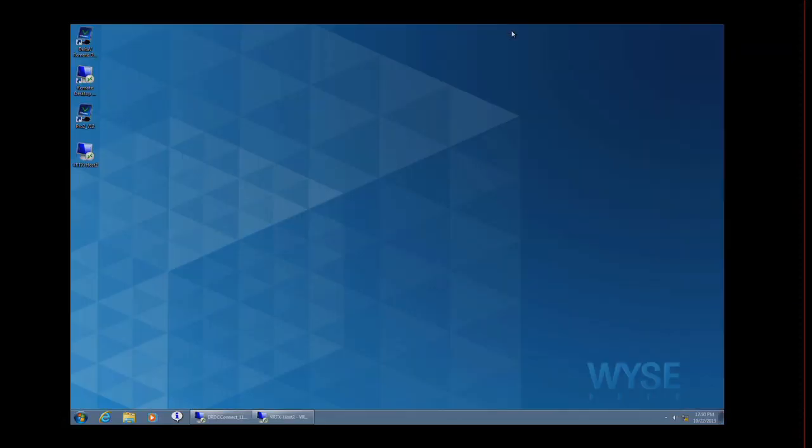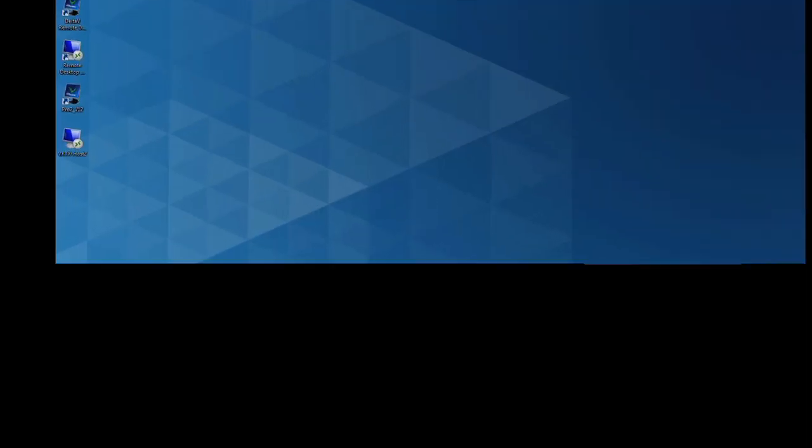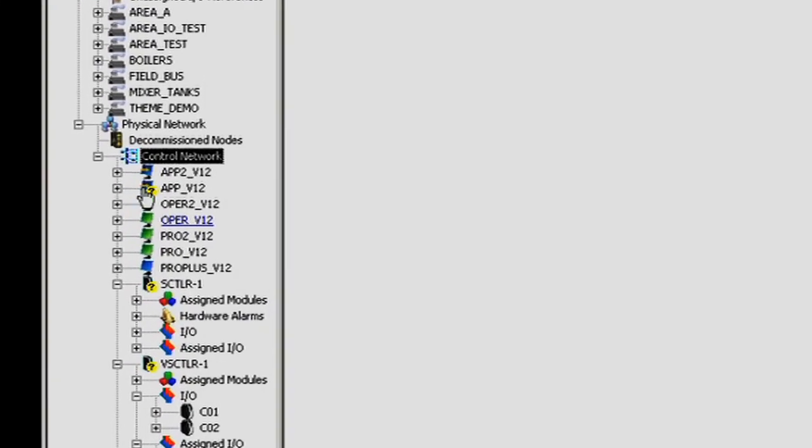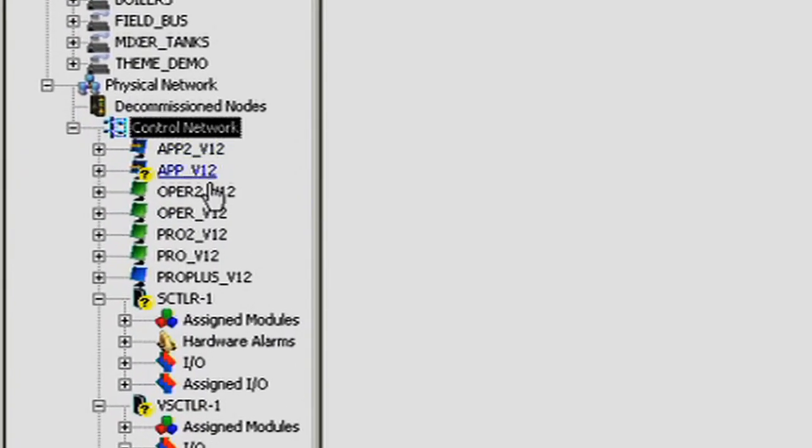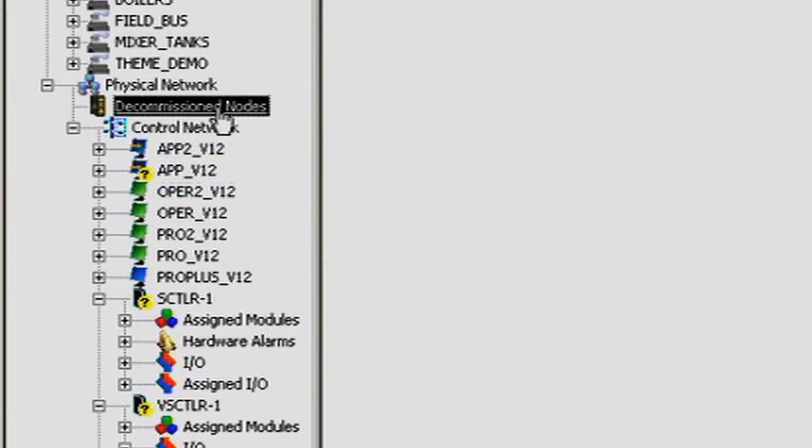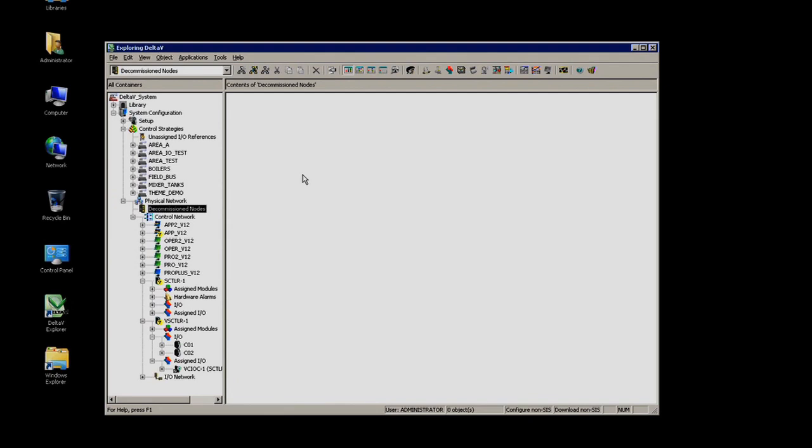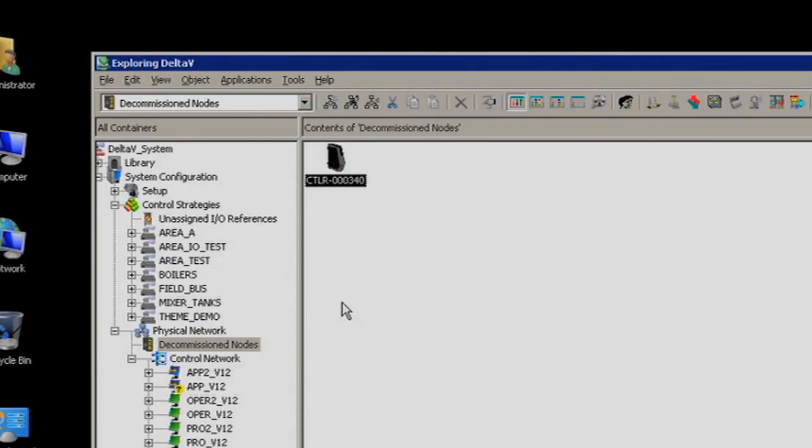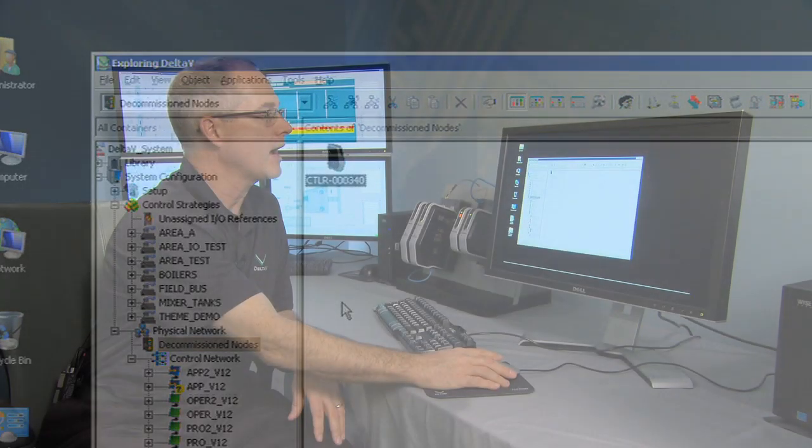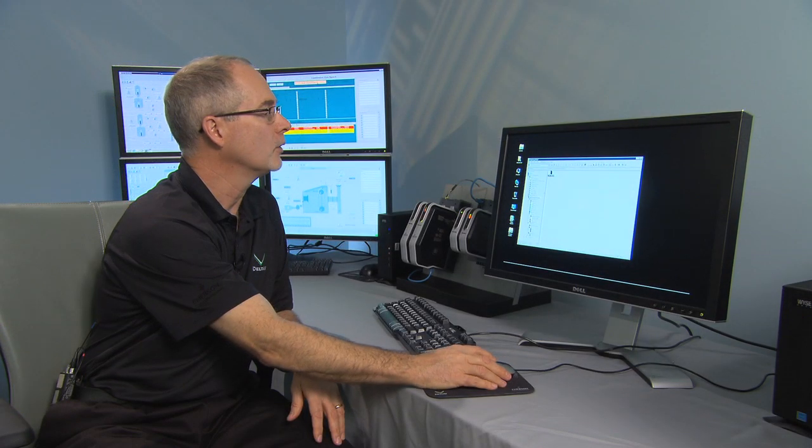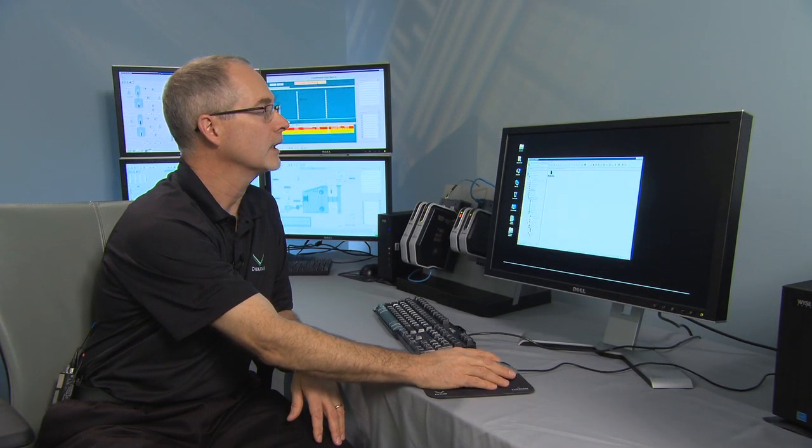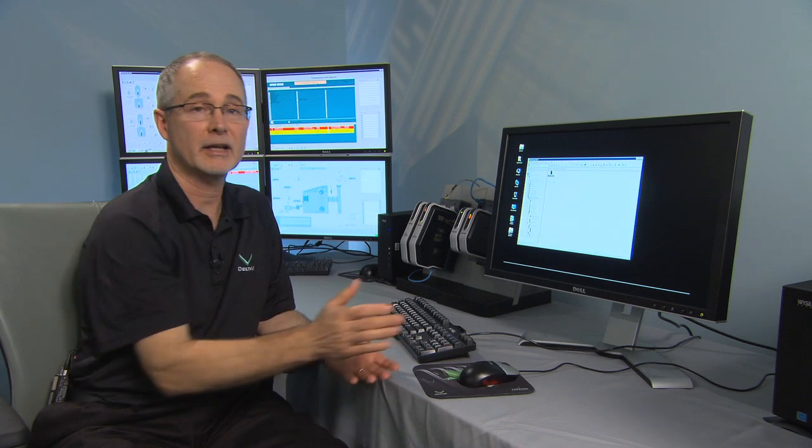So if we pop over back to our professional station, which we can view from this same thin client, and we look under the decommission nodes, what we'll see is a new virtual controller pop up, just like a physical controller, that we created from those templates. Okay, so here's our virtual S-Series controller that Delta V has seen, and we could drag and drop that to our control network, and it would behave just like a normal S-Series controller.